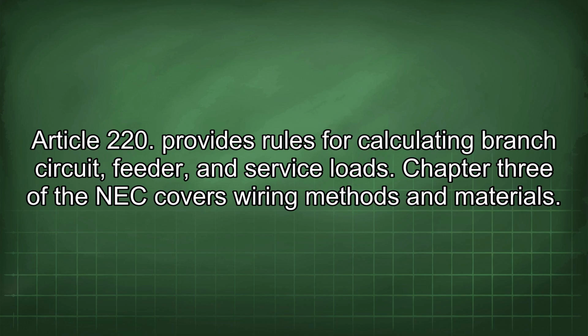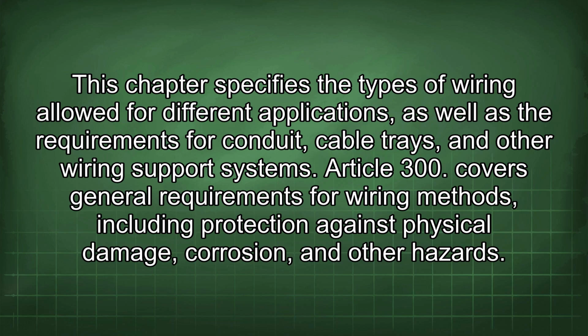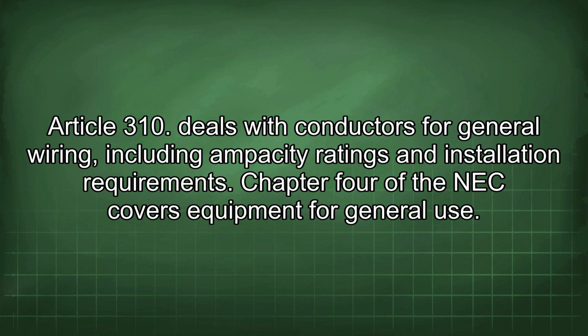Chapter 3 of the NEC covers wiring methods and materials. This chapter specifies the types of wiring allowed for different applications, as well as the requirements for conduit, cable trays, and other wiring support systems. Article 300 covers general requirements for wiring methods, including protection against physical damage, corrosion, and other hazards. Article 310 deals with conductors for general wiring, including ampacity ratings and installation requirements.